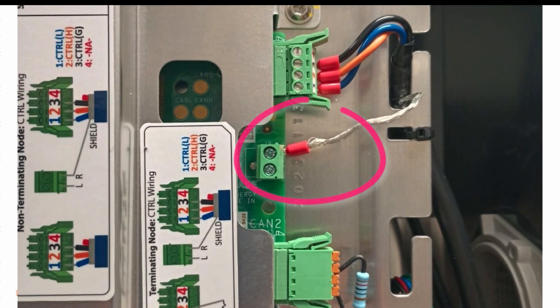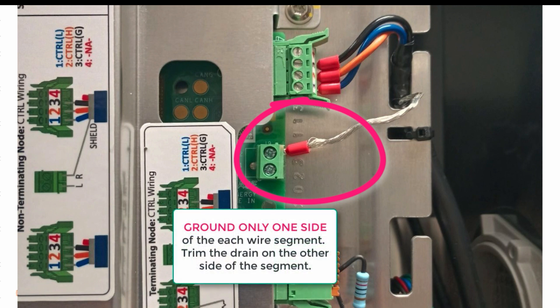Connecting the drain wire. The drain wire on each control cable segment between devices must be wired to ground at one side or the other of the cable. The drain wire on the other side can simply be trimmed off.